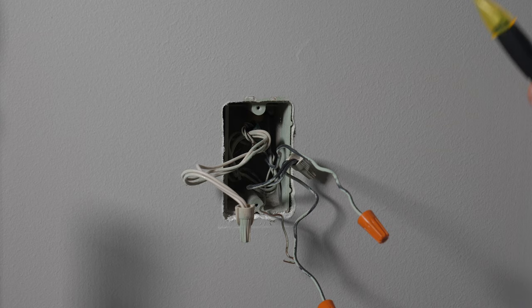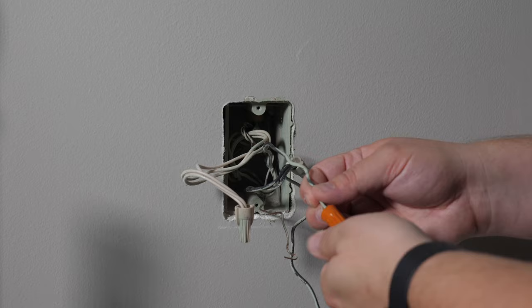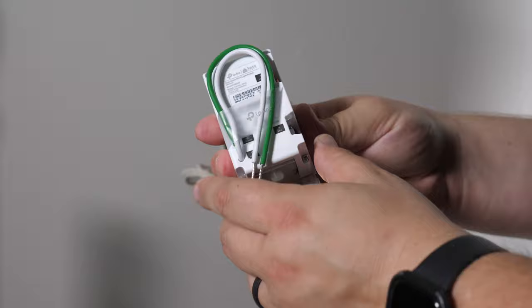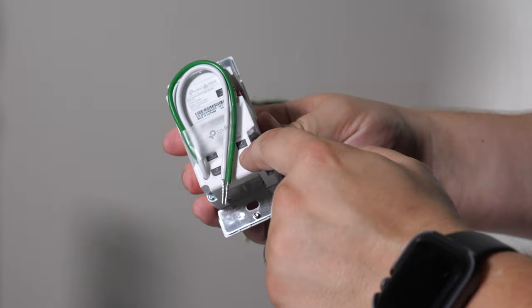Now that the power is off again, I'm going to go ahead and take these wire nuts off. To get this faceplate off, it looks like we have to pry up from the bottom because we've got this little cutout here. In the back here you've got two wires—the white goes to our neutral, green goes to ground—and then at the bottom this is where we put our line, and the top is where we put the load or where the light itself is being powered from.